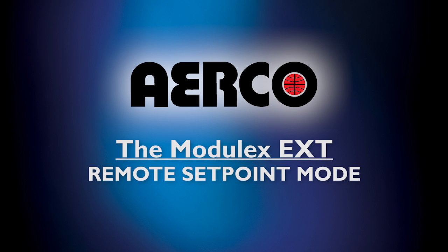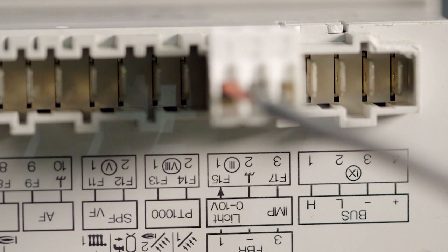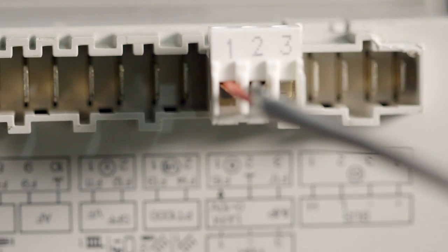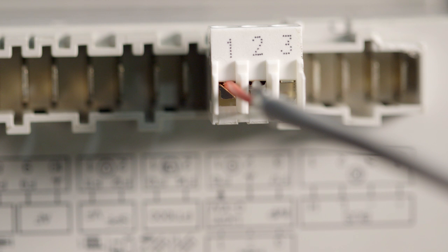Remote set point mode allows you to control the boiler's set point by using an external control signal. In order to operate in the 0 to 10 volt remote set point mode, the remote signal source for your unit must be wired to terminals 1 or F15 and 2 or GND of connector number 3 on the rear of your controller as shown here.